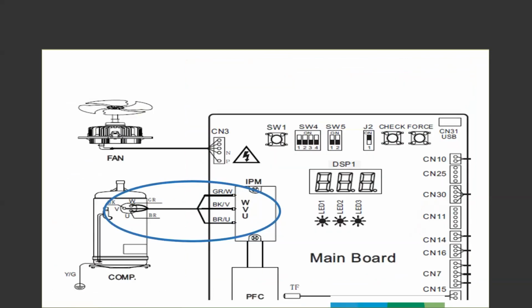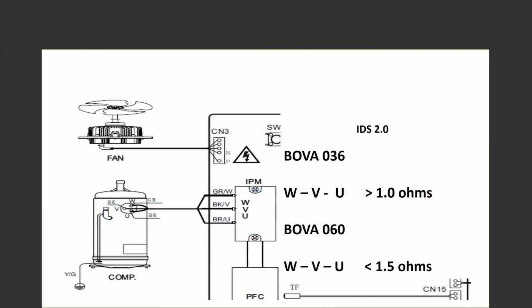On the compressor, the V, the U, and the W, same type of scenario there. Different compressor. This compressor is a GMCC compressor, Guangdong Meizhi compressor. It is manufactured by the largest manufacturer of compressors in the world. This compressor allows us to have some more BTUs in the wintertime, allows us to have a little bit less sound, but it does ohm out different than the 1.0.